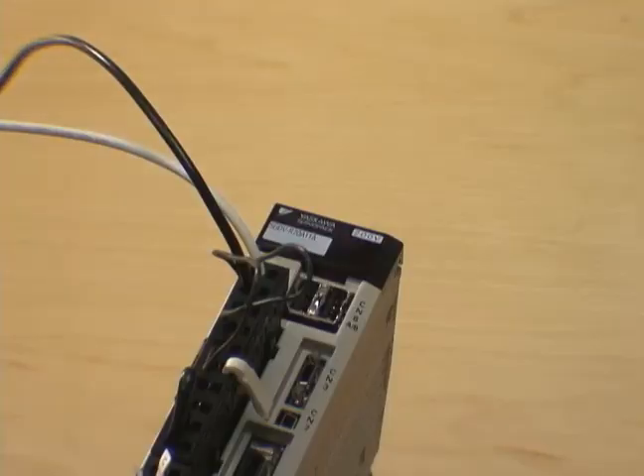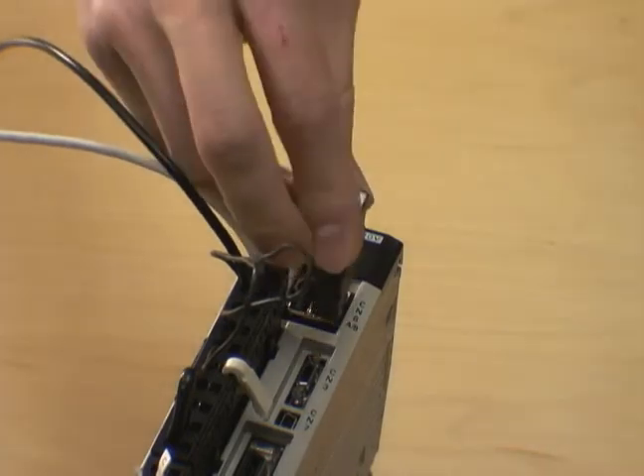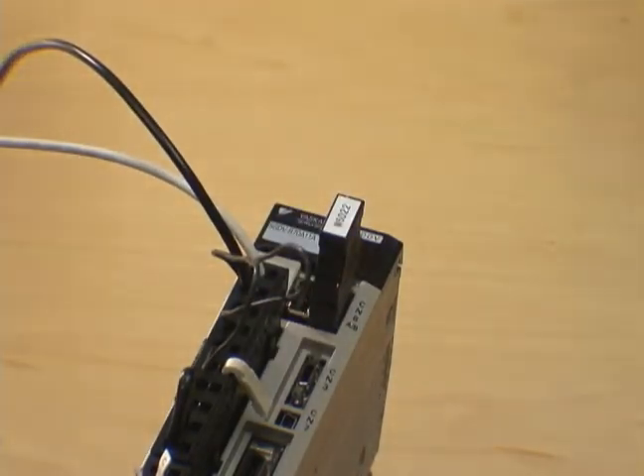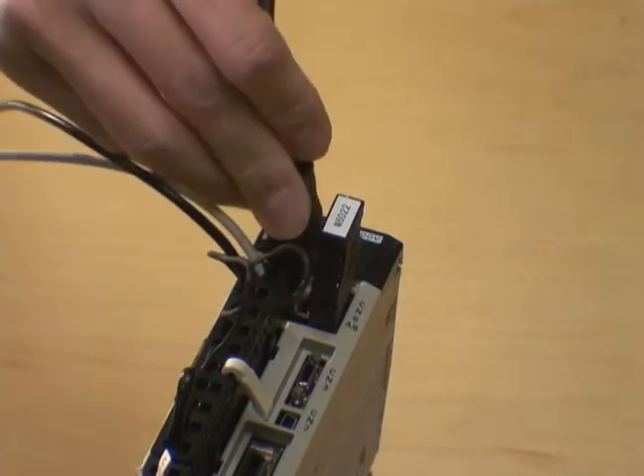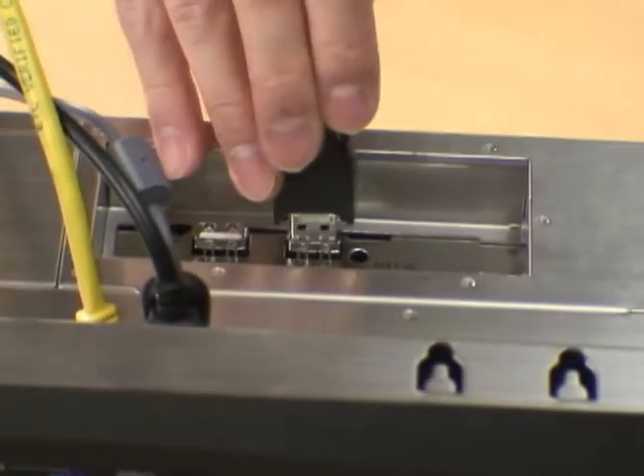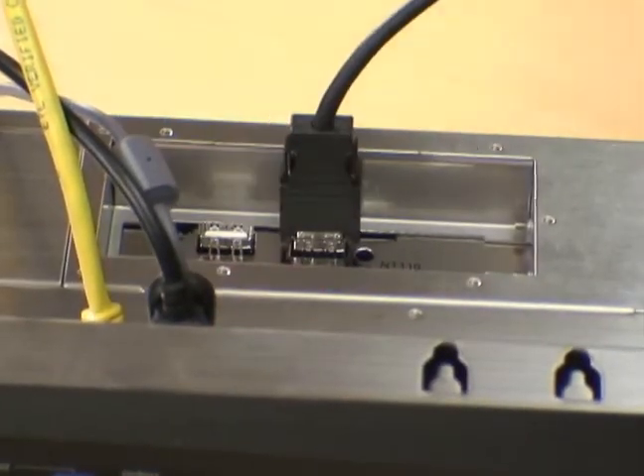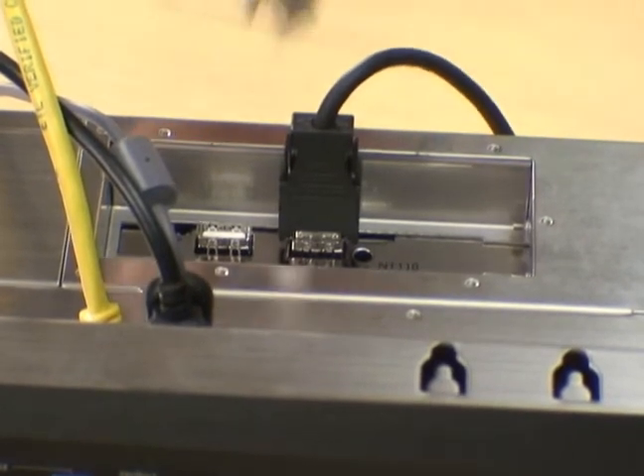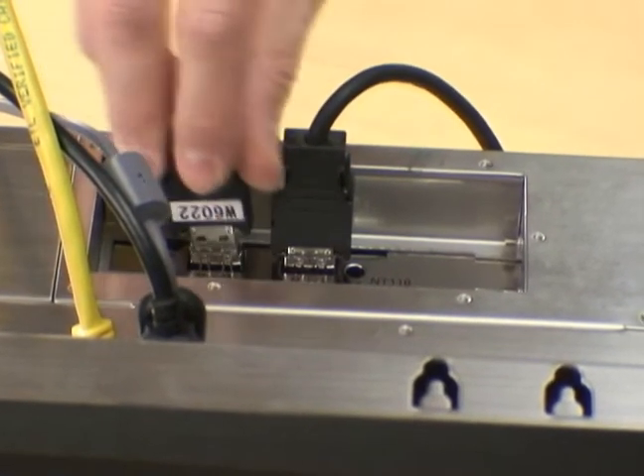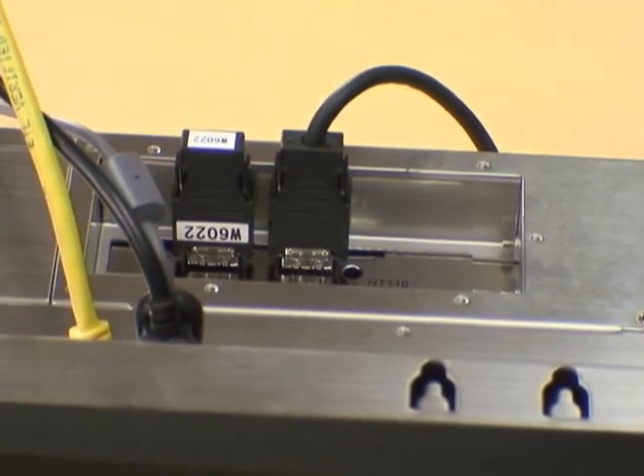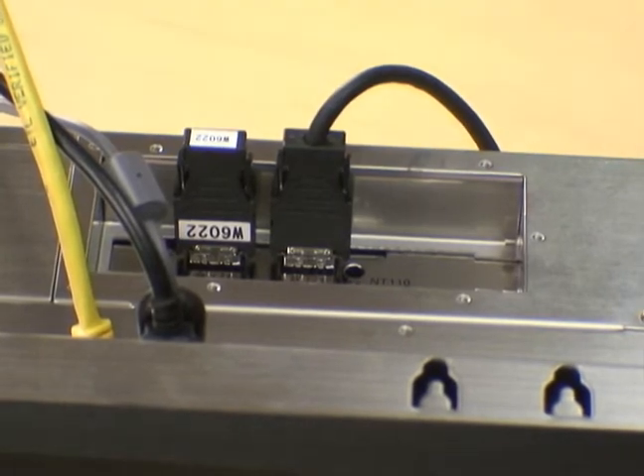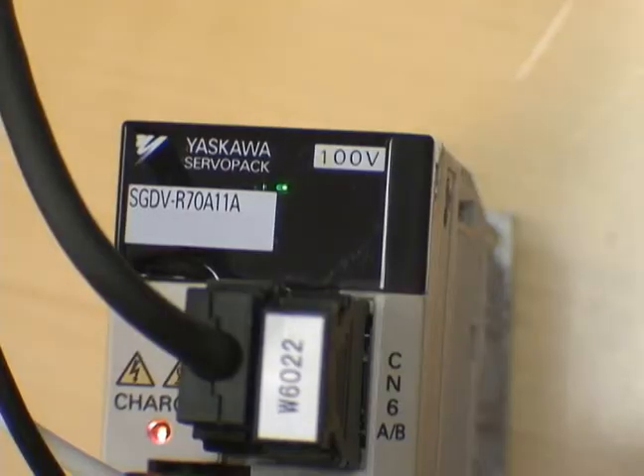Connect a MechaTrolink terminator into the communications port of the amplifier. And connect a MechaTrolink network cable to the other port. Connect the other end of the MechaTrolink network cable to the PCI network card and a MechaTrolink terminator to the other port. Turn on the power going into the amplifier.